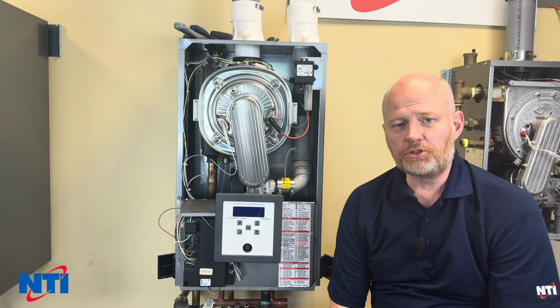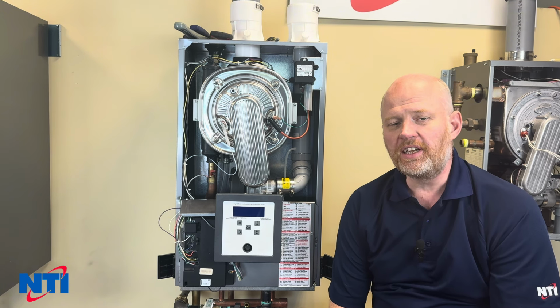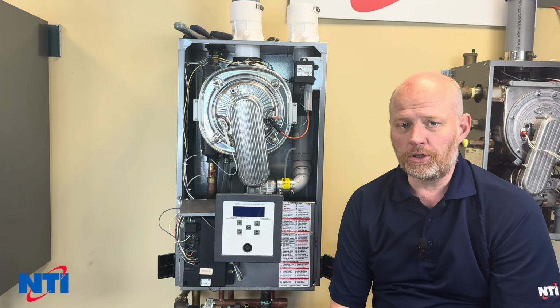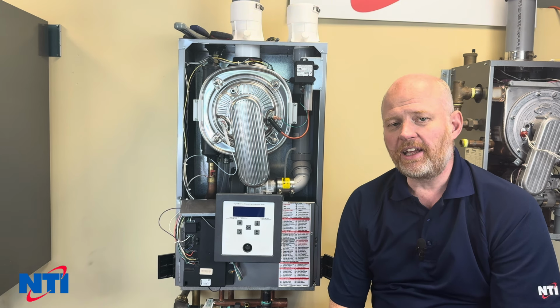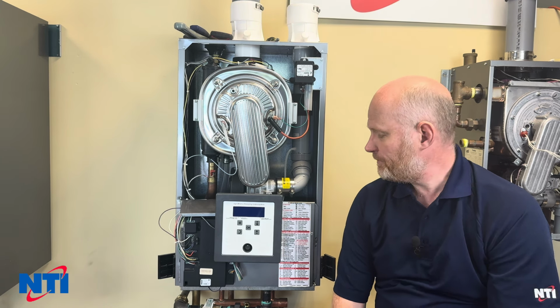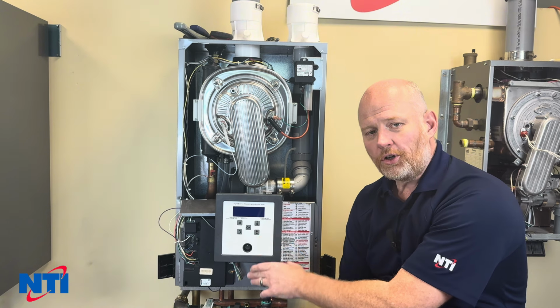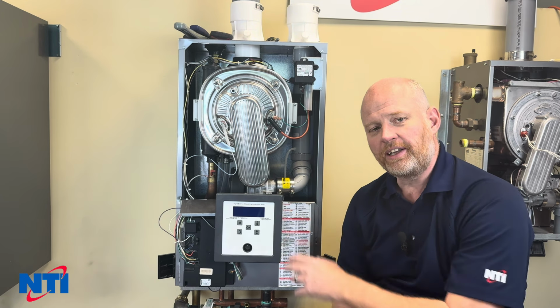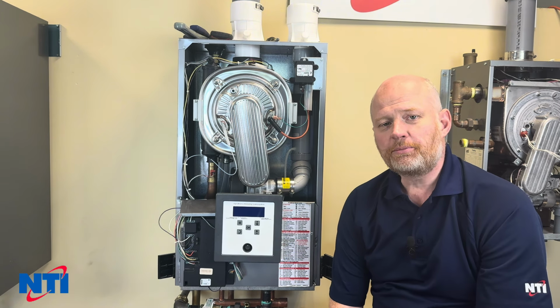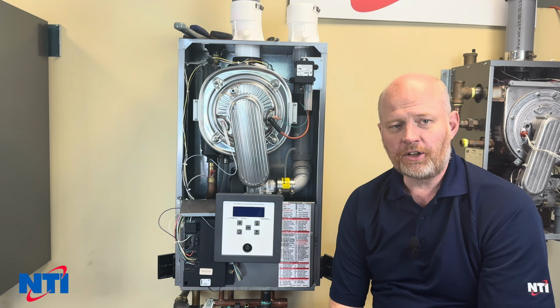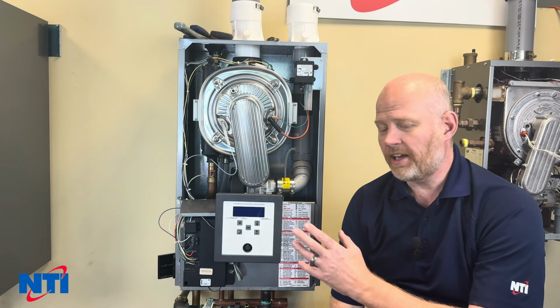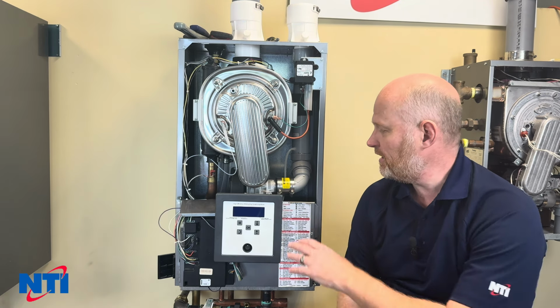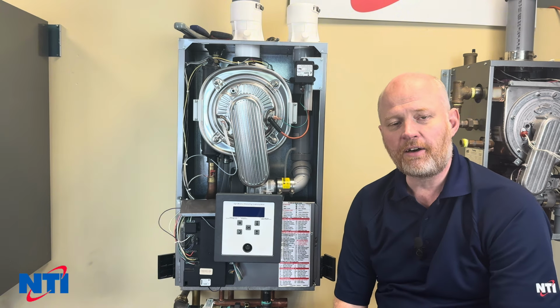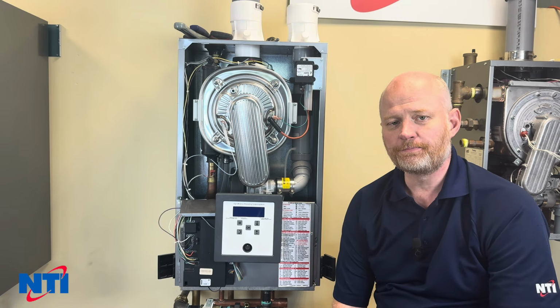You'll want to start by draining the product down on both the domestic water side and on the boiler water side. I would recommend that when you're draining the boiler side, you turn the power on and off several times. That will actuate the internal diverting valve, to make sure that as much water is drained out of the boiler as possible. You don't want to get that plate off and find that the diverting valve was holding half a gallon of water inside the pressure vessel.